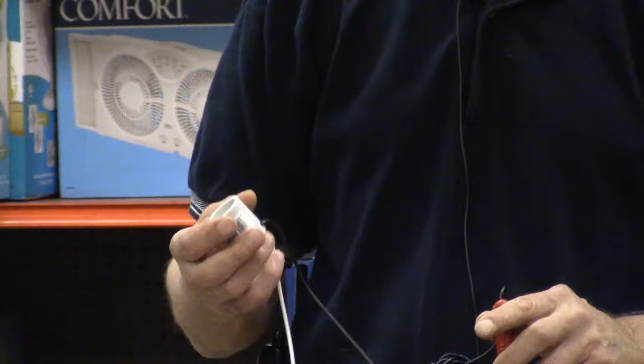Again, I'm on my hot wire, all right, so that's the center contact. Is that good? Yeah. Then you get into the neutral, and on your light sockets that's the threading. You don't really want to reverse it, by the way, because you can get shocked taking a light bulb out if the wiring's reversed. So is the threading good? Of course, so it's a good light socket.